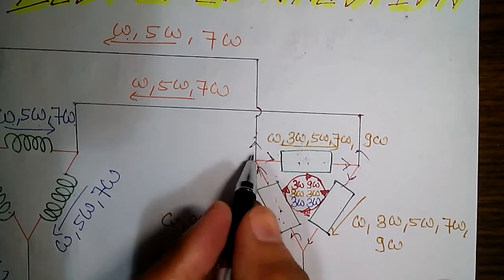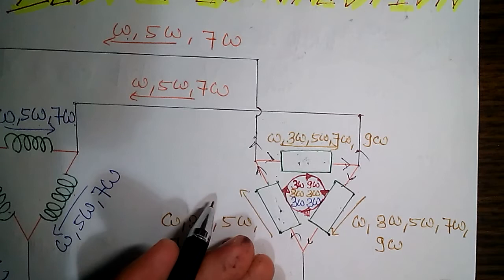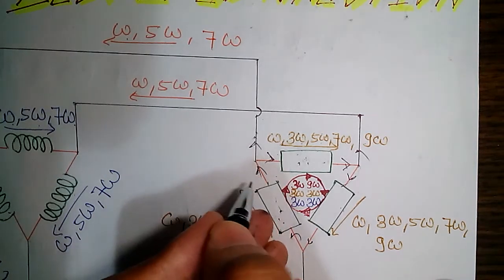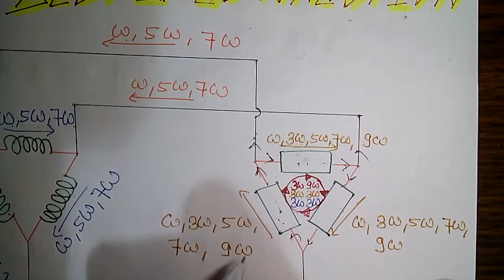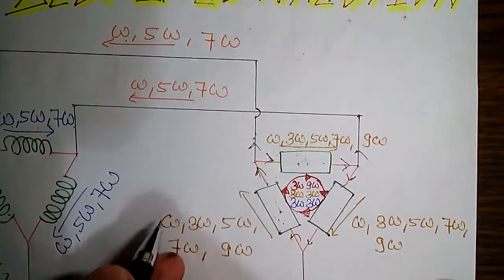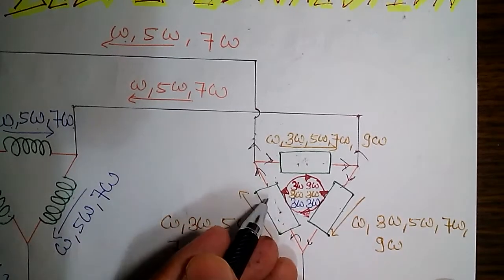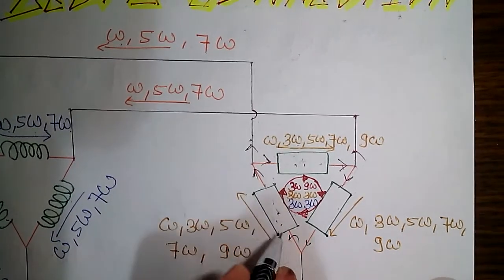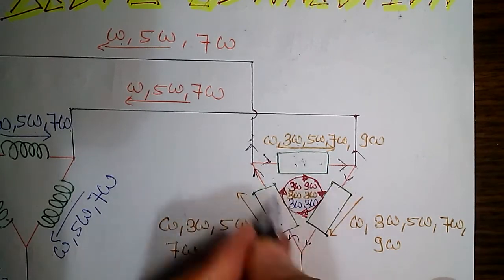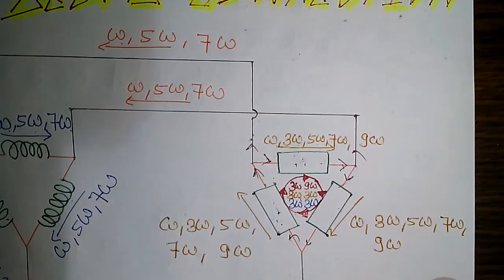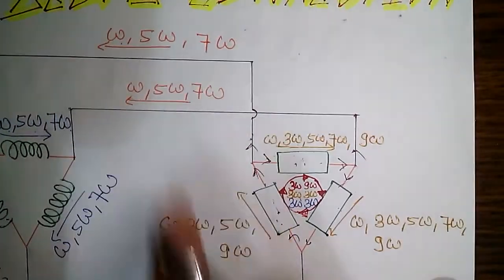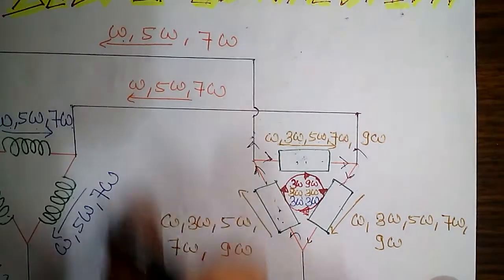All my other harmonics will be going into the line, because for all other harmonics they are not in the same phase and their values are not the same for all R, Y, B phases. So some part of them will also be going into the line. But for the third harmonic the case is different — the value of R, Y, B current is the same, so they all revolve around in this circle only and will not go into the line.